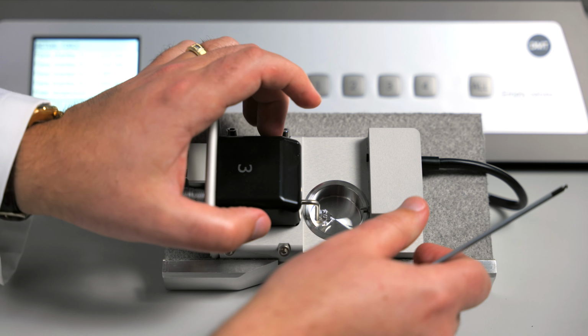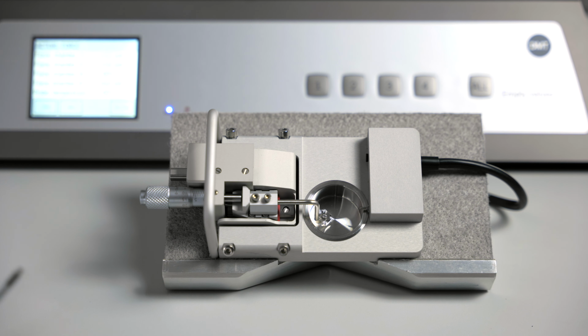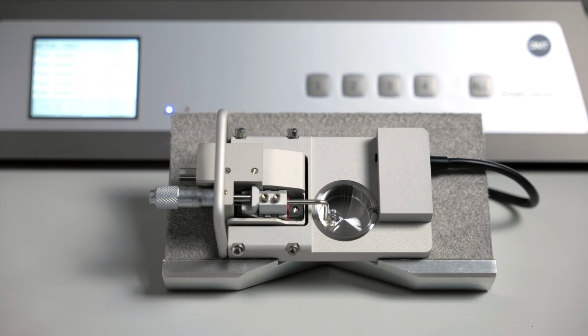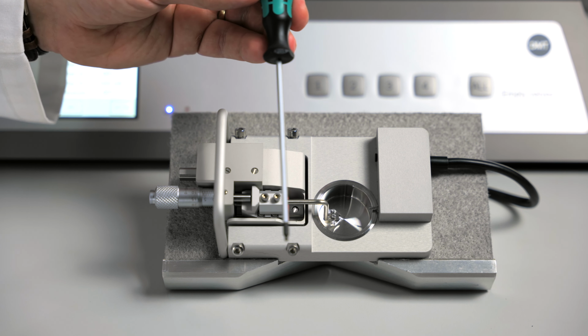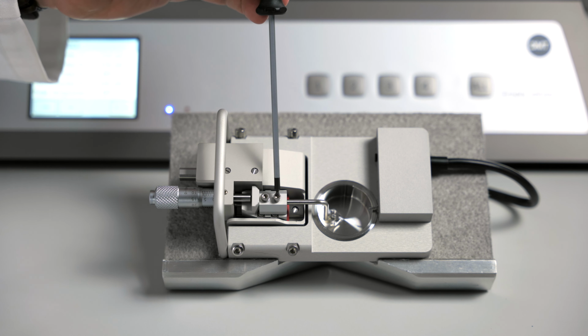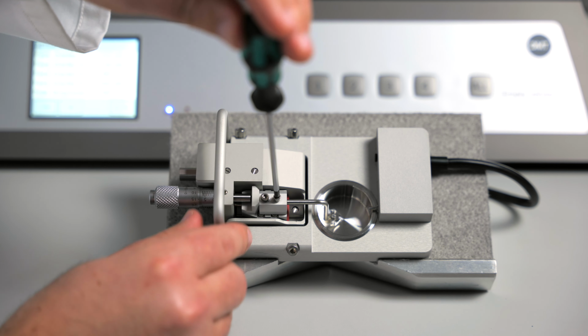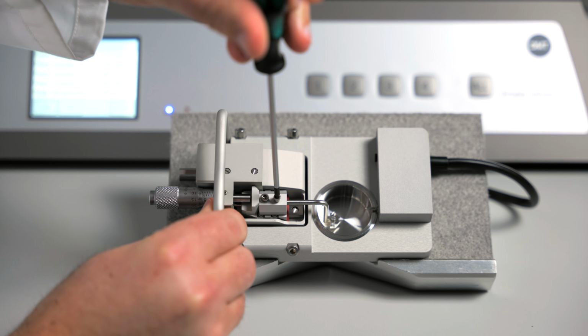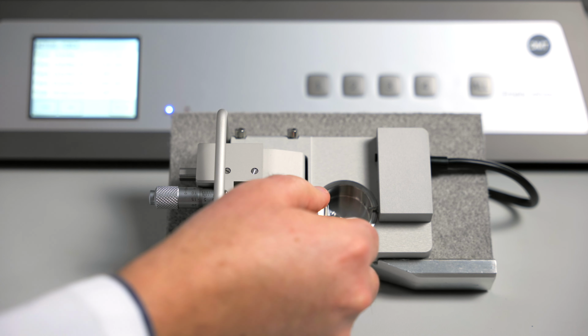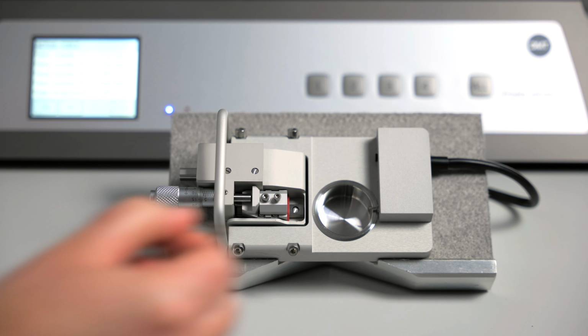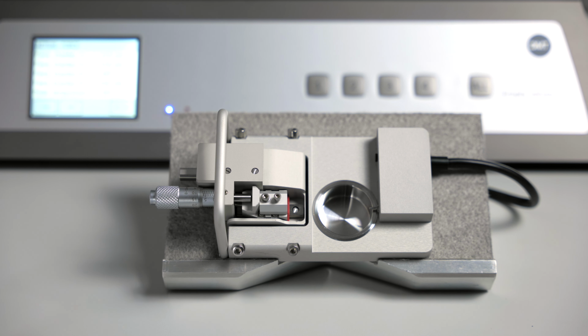You can then remove the black cover. You will then use your ball end screwdriver to loosen the first screw closest to the chamber. You can then slide out the positioner side mount. Replace the mounts in the reverse order, starting with the positioner side.